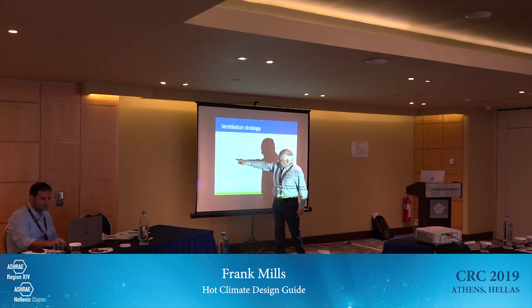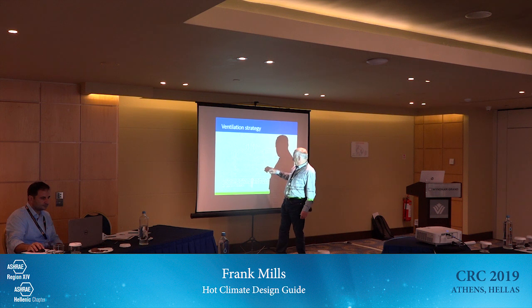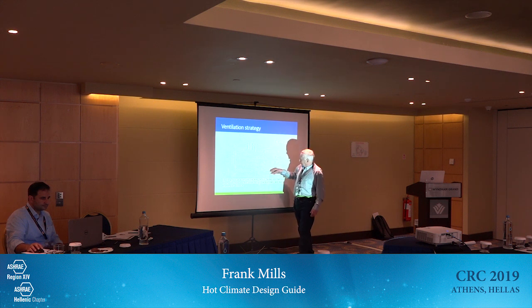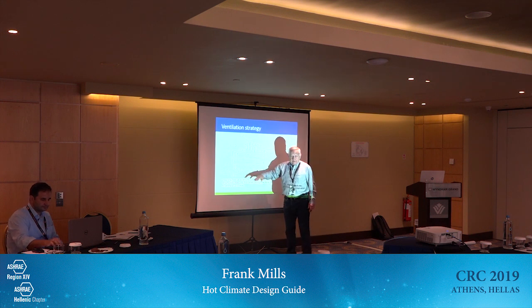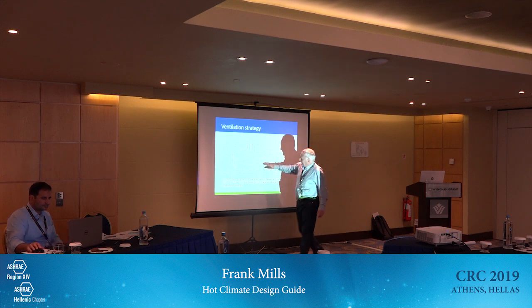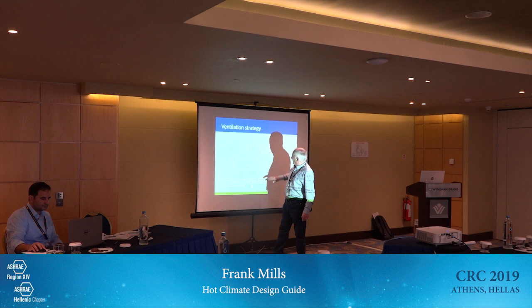And when it gets to the edge here, it goes into this chimney where it goes up to the roof and then out through this outlet. I don't know if you can see the numbers here, but it's saying it'd be 27 degrees C by the time it gets here. So it's coming in at 17 degrees C into the space. The space is adding heat. The heat is the lights, people, equipment. And then that airflow, having reached 27, flows up and outside the space there.